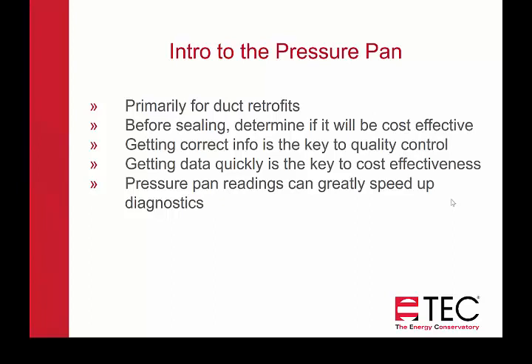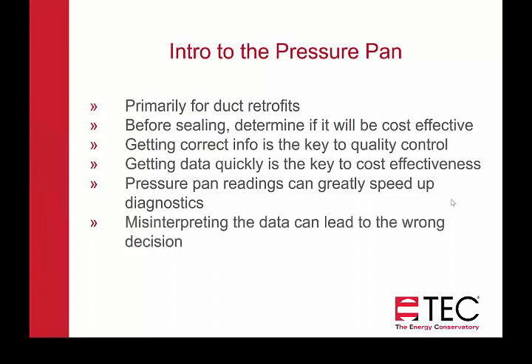Pressure pans can greatly speed up the cost effectiveness — not only to help determine if it's worth spending the time and money to seal those ducts, but also speeding up the diagnostics part. If you misinterpret the data, it can lead to the wrong decision. It really becomes very important to make sure that you understand what the readings mean in this house, with how you have it set up and with pressures in adjoining spaces that contain ductwork.